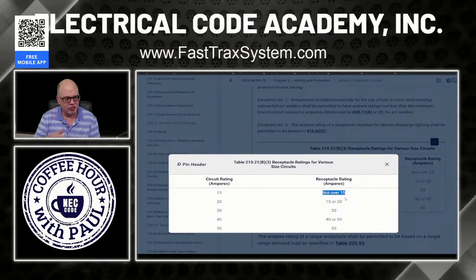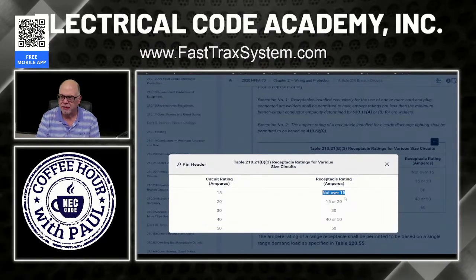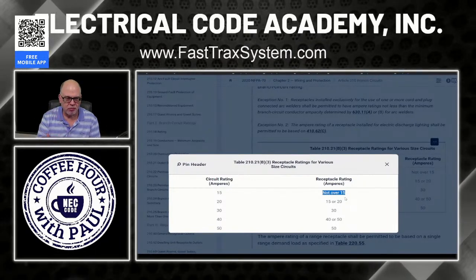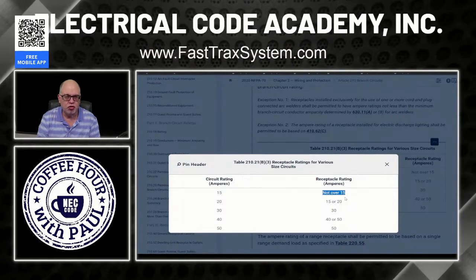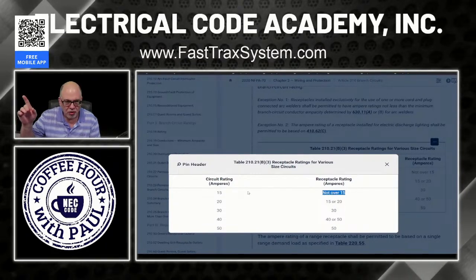And the bedroom, obviously, is going to be an AFCI 210.12(A) requirement. Bedroom is in that list. And they're 15 amp receptacles. Then it would be a 15 amp rated overcurrent protective device and a 15 amp rated duplex receptacle. Make sense? All right, we'll leave that there on the screen, and we'll go back to the code material so we can look at it.